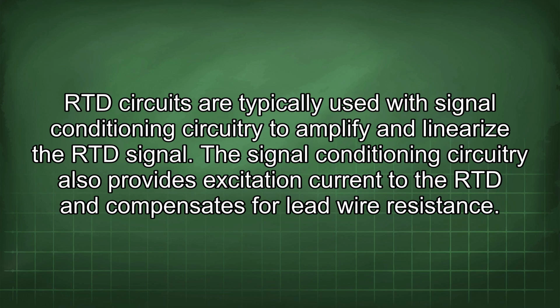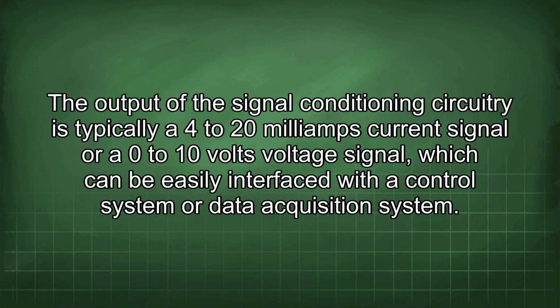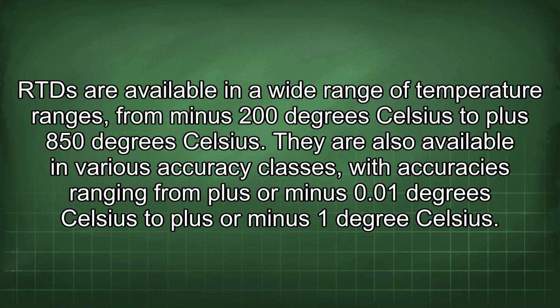RTD circuits are typically used with signal conditioning circuitry to amplify and linearize the RTD signal. The signal conditioning circuitry also provides excitation current to the RTD and compensates for lead wire resistance. The output of the signal conditioning circuitry is typically a 4 to 20 mA current signal or a 0 to 10 volts voltage signal, which can be easily interfaced with a control system or data acquisition system. RTD are available in a wide range of temperature ranges from -200 degrees Celsius to +850 degrees Celsius. They are also available in various accuracy classes, with accuracies ranging from plus or minus 0.1 degrees Celsius to plus or minus 1 degree Celsius.